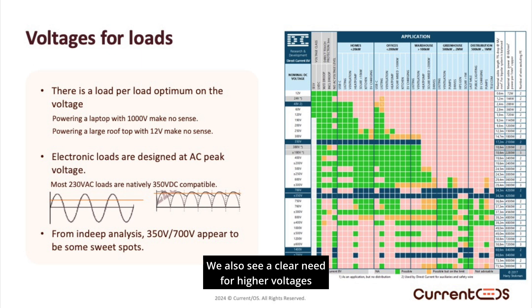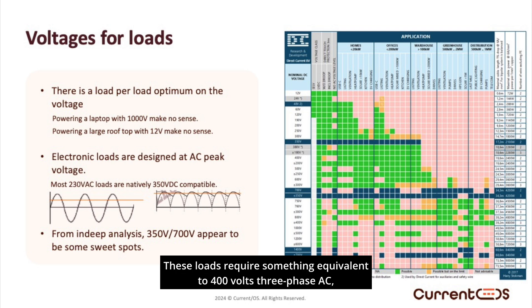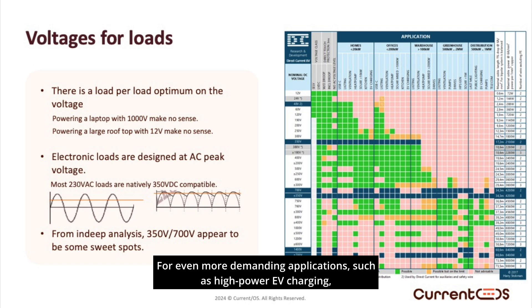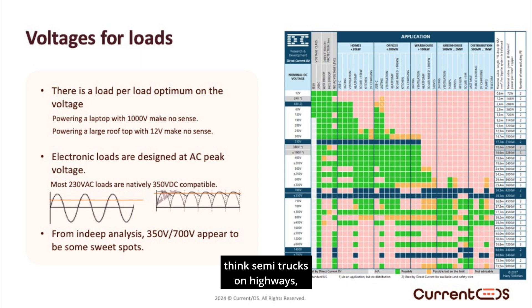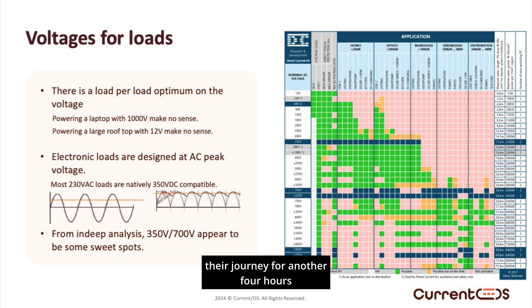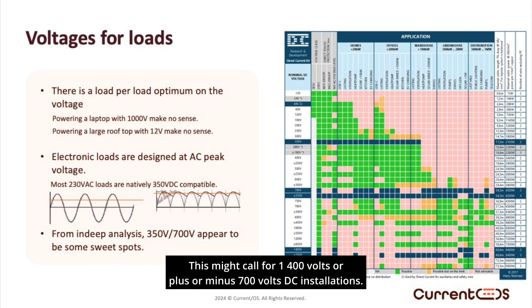We also see a clear need for higher voltages for more powerful loads, such as EV chargers or heat pumps. These loads require something equivalent to 400 volts three-phase AC, but in a DC system. For even more demanding applications, such as high-power EV charging — think semi-trucks on highways — we observe the need for much higher voltage bands. For example, charging a truck in 45 minutes so the driver can resume their journey for another four hours requires megawatts of power. This might call for 1,400 volts or plus or minus 700 volts DC installations.